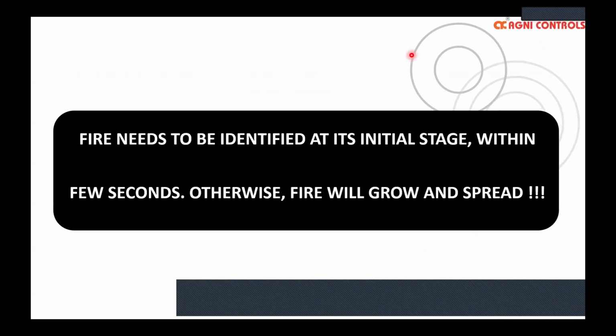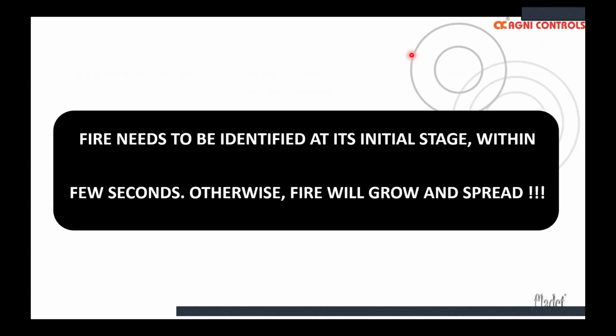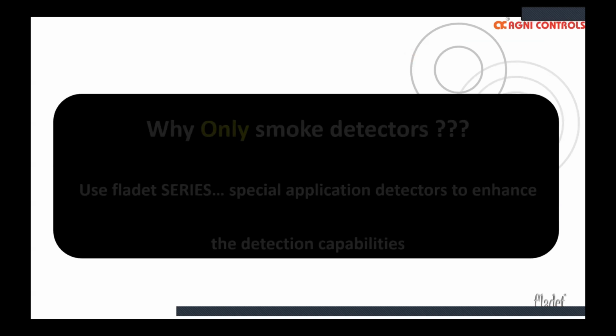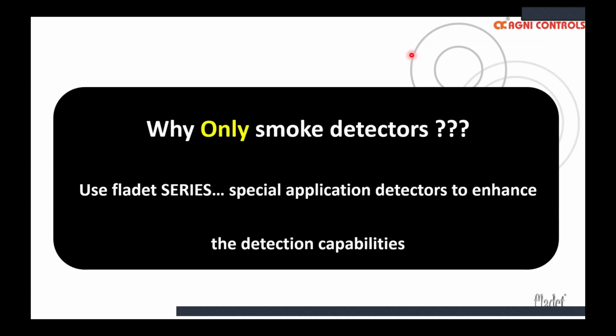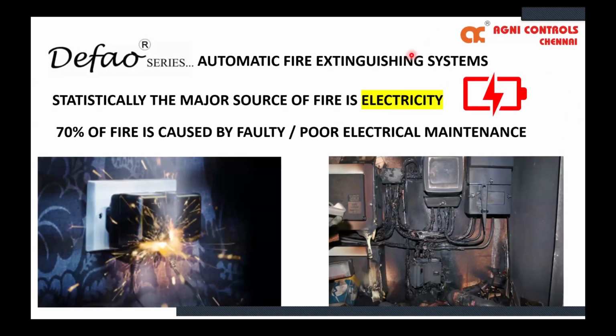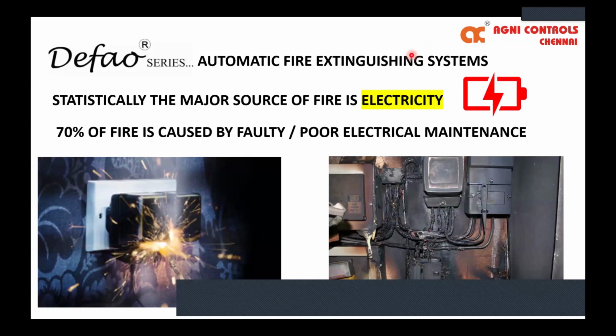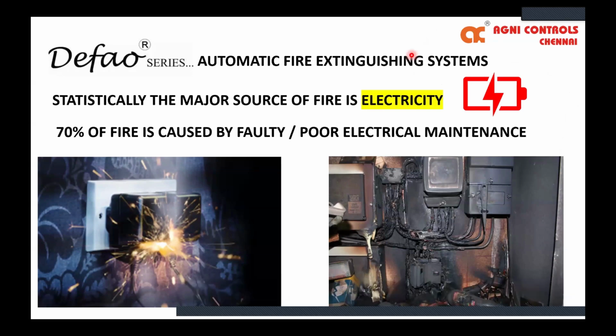So fire needs to be identified at its initial stage, within a few seconds. Otherwise, as I explained in the animation previously, once it grows, it's very, very difficult to contain. So why only smoke detectors? Use special application flame detectors to enhance the detection capability. When we're talking about enhancing flame detection, it is only fair for me to also include the fire detection and the automatic extinguishing system.